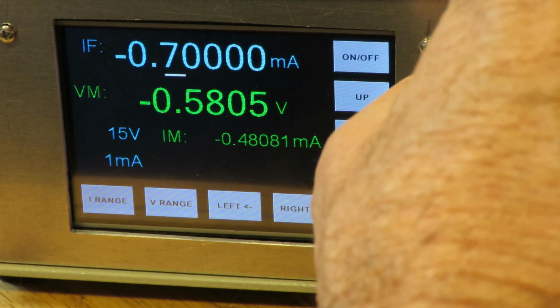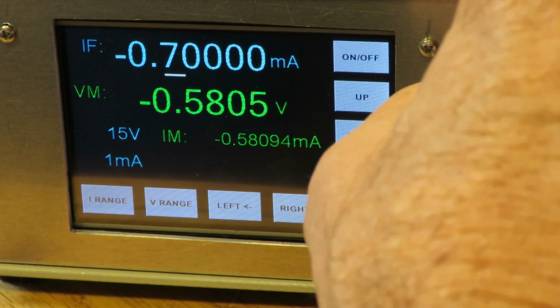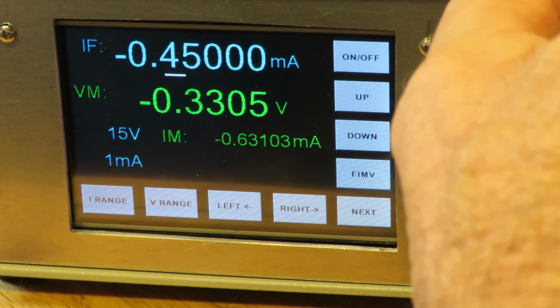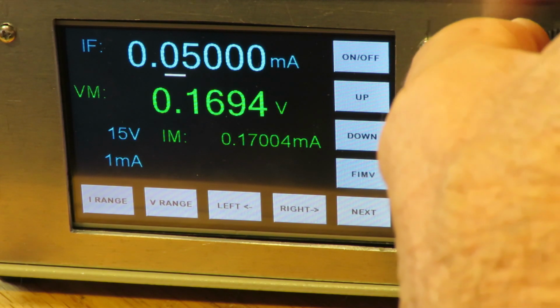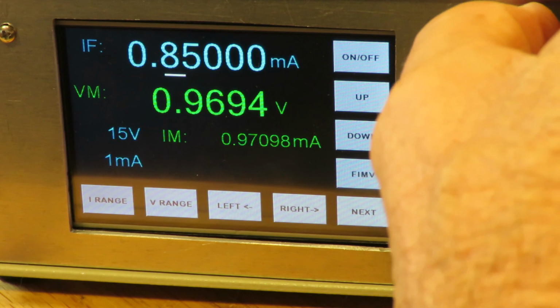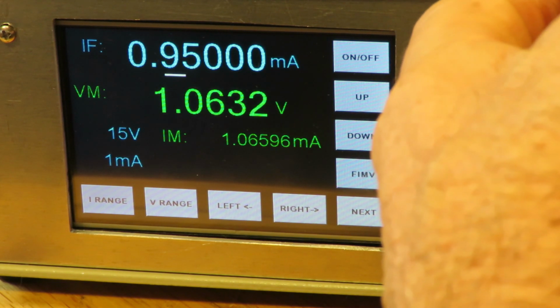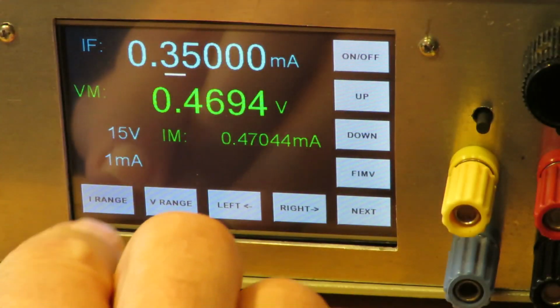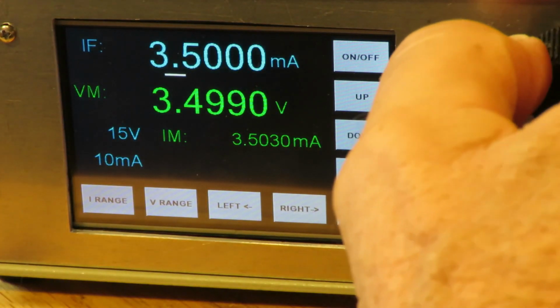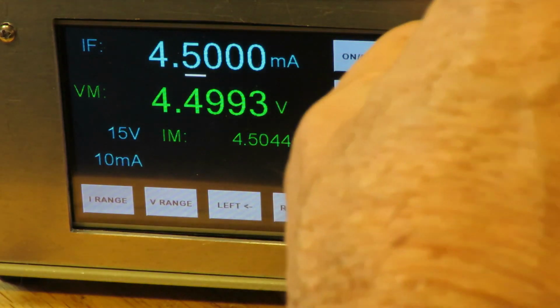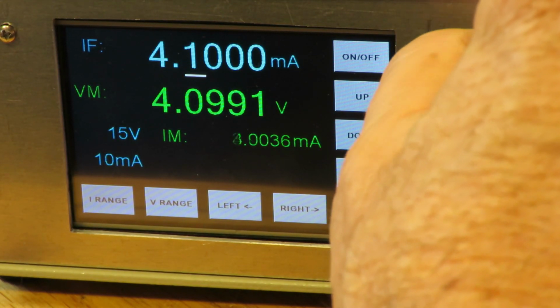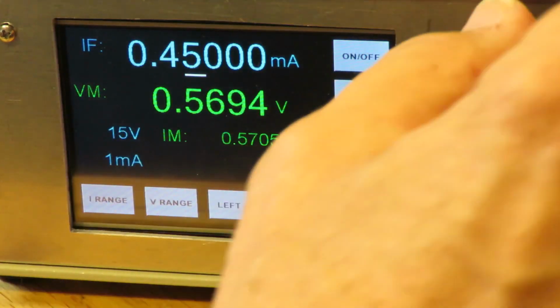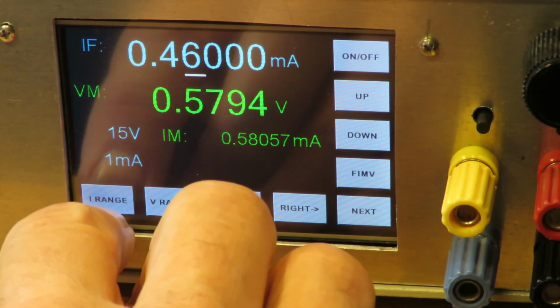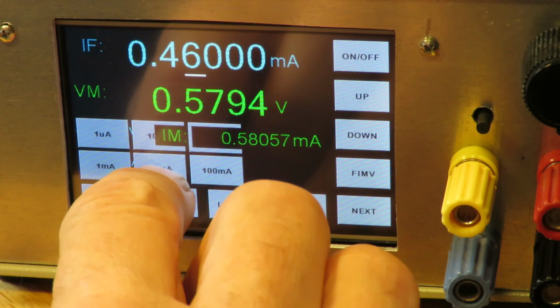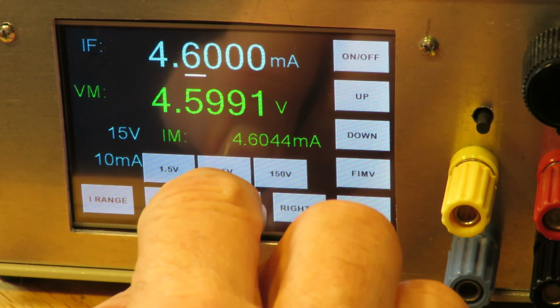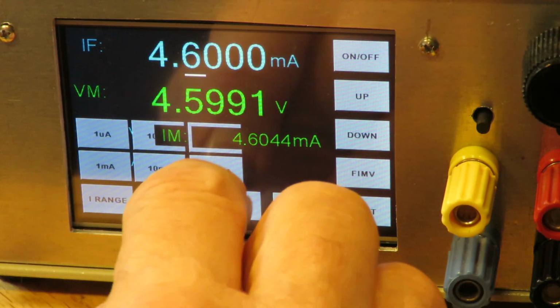There's the voltages as a function of the setting. I noticed that there's an error on the force voltage. Okay. Let's try higher current range. So this is the 10 milliamp range. Yeah, I think the 1 milliamp range must not be calibrated. Yeah, I got a pretty significant error on the 1 milliamp range. 10 milliamp range, and here's the 100. Oops. Let's go back to 15, and then current, high current.